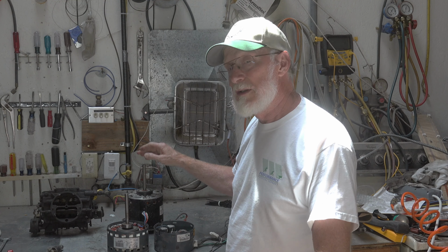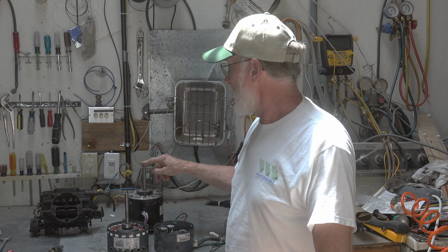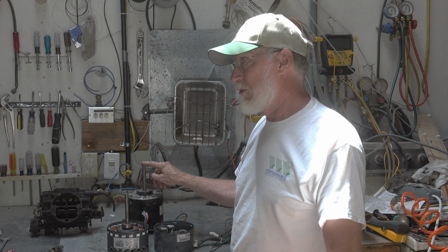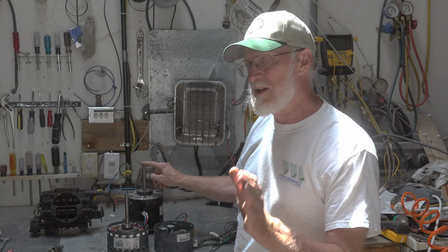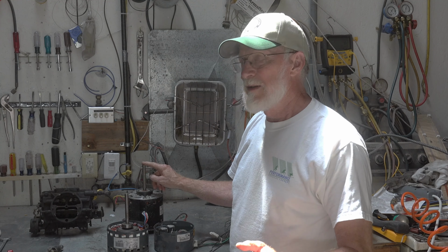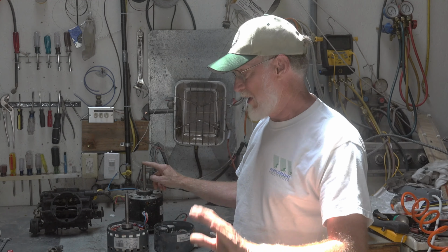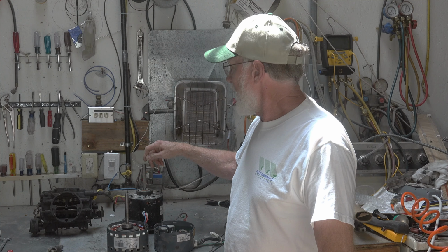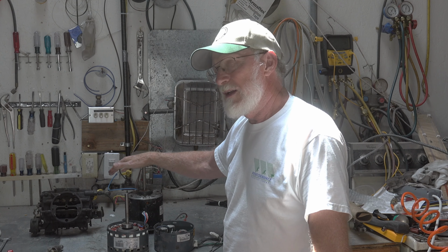And in fact, if I were to take this motor and instead of running it on 60 cycles a second, now most people say hertz, I'm saying cycles per second because it's the number of AC cycles that happen per second. Positive, zero, negative, zero. Okay? If I ran this on, say, 30 cycles per second instead of 60, it would go half speed.